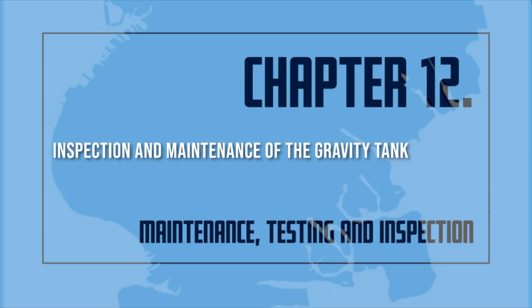The outside of the gravity tank will require local patching. A complete finish coat of paint is needed when the paint has weathered thin. A new coat of paint also improves the appearance of the tank after it has been patched. Painters shall be careful that scrapings or other foreign materials do not fall down the outlet into the sprinkler piping. The discharge outlet may be covered for protection during repairs. Only a few sheets of paper or a paper bag tied over the end of the settling basin stub should be used. The paper should be removed immediately after the job is finished.